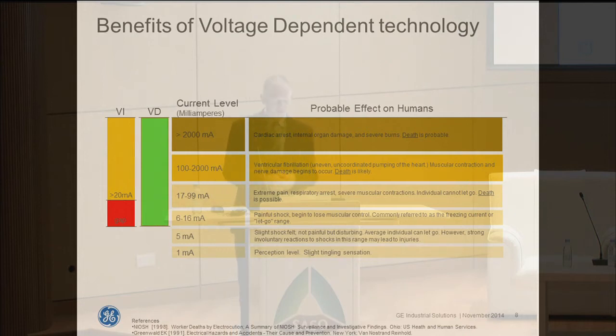And I was mentioning just a little bit ago about a chart which really helps us understand the different thresholds for when a body is subject to an electrical shock and the different levels. And so you can see on the chart where the UL definition of the trip point at 6 milliamps on a voltage-dependent device will really identify that you've got below the 6 milliamps, it's a very slight shock, maybe like a static shock, but it's not something that's really going to harm a typical human. And as we start to get higher in the chart, you start to have more dramatic effects on the human body.